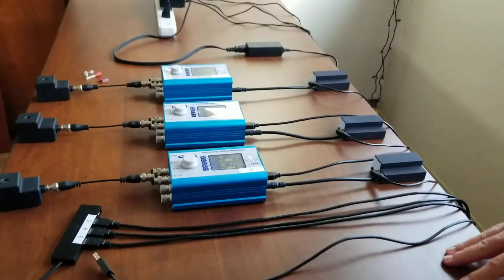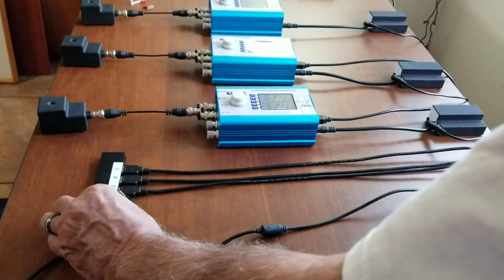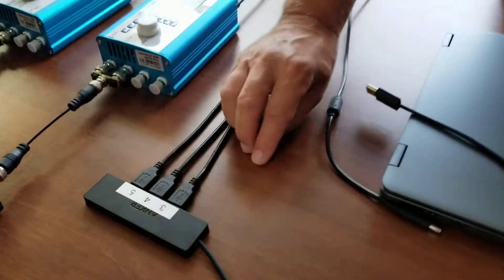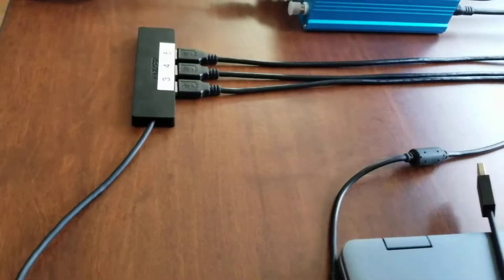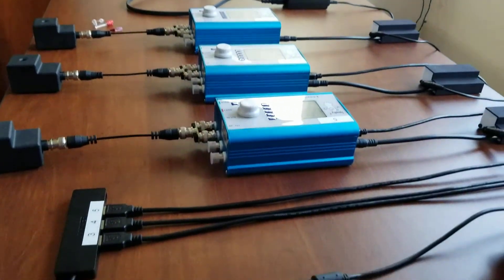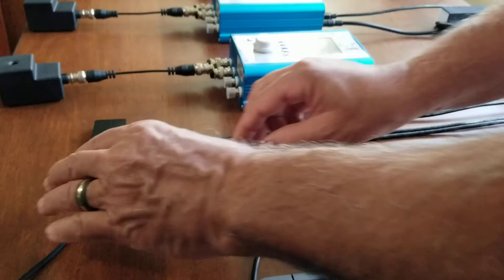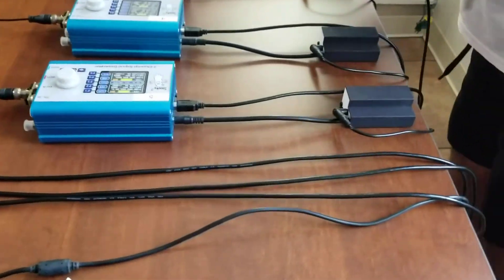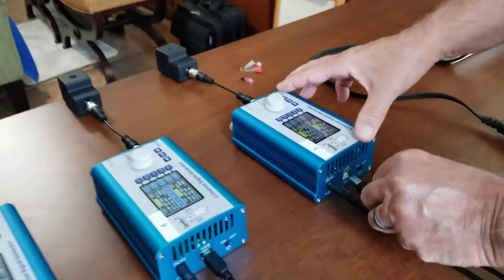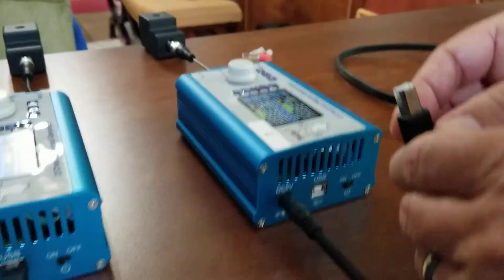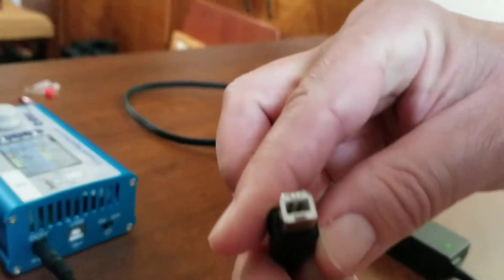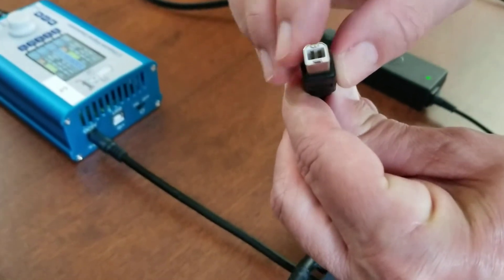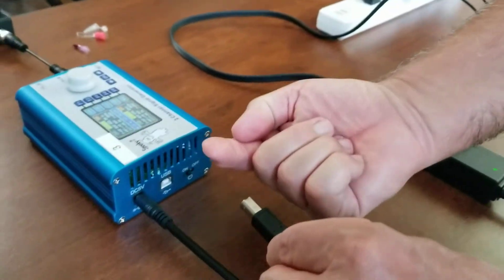Since this is a triple system, it's going to ship with a little USB hub. And the USB hub is going to be clearly marked, three, four, five, because this is a triple system. We need to keep that order. So the cable from three, we're going to connect into the USB connector. You'll notice here, the connector is a square with two chamfered edges on the top. The two chamfered edges go up.